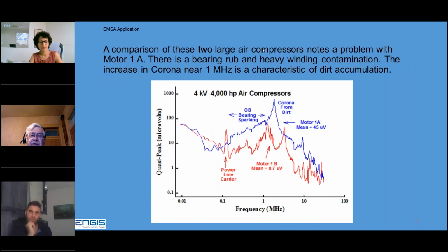Here's another comparison of 2 large air compressors at a plant. This 1B motor, here's a power line carrier, radio transmitter, AM radio stations, a peak here, which is dirt starting. Pretty well stops at about 30 megahertz. The other motor, the 1A motor, had very high readings right above 1 megahertz. And that's a typical signature for contamination on stator windings, high corona readings near 1 megahertz.